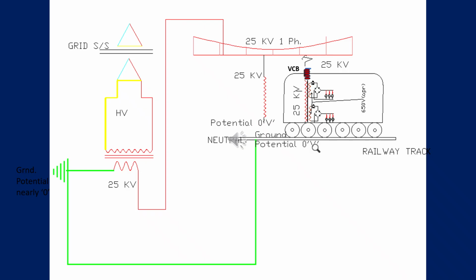Again, if I repeat it, we are getting 3-phase supply from the grid substation, and with the help of the transmission line we are receiving it in the traction substation. From there we are taking two phases. Here we have shown red and yellow, and then it is connected with the single phase transformer, two phase incoming, but it is a single phase transformer. We are stepping it down to around 25 kV, but the voltage must be less than 27.5 kV maximum, and minimum also some limit is there, that is 22 point something in the traction substation.